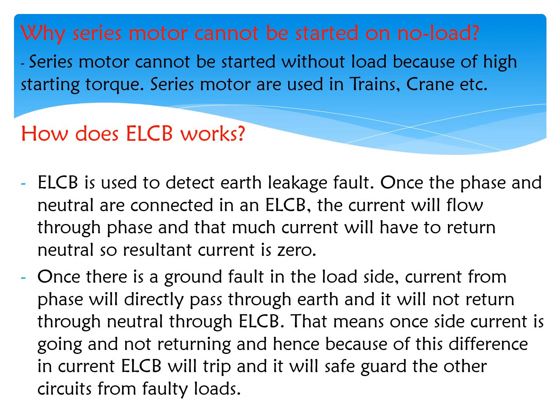Once the phase and neutral are connected in an ELCB, the current will flow through the phase and the same amount of current will have to return through neutral, so the resultant current in the ELCB tripping coil is 0. Once there is a ground fault on the load side, the current from the phase will directly pass through the earth and it will not return through the neutral through ELCB. That means one side current is going and is not returning. Hence, because of this difference, the ELCB will trip and it will safeguard the other circuits from the faulty load.